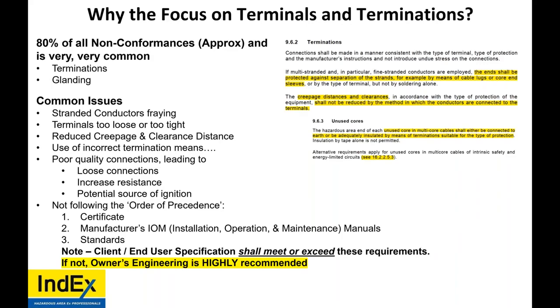When you're installing a terminal and your end sleeves or whatever you may use, you have to follow the certificate of the terminal, the manufacturer's installation, operation and maintenance manuals, and the pertaining standard to the EX protection type. The client end user specification shall meet or exceed these requirements. If not, I highly suggest an owner's engineering review on behalf of the end user, perhaps by a third party.